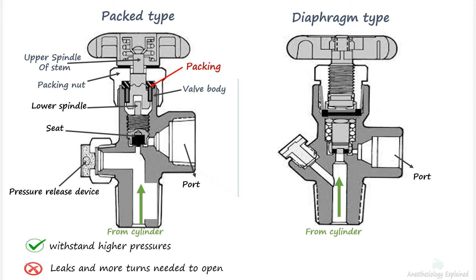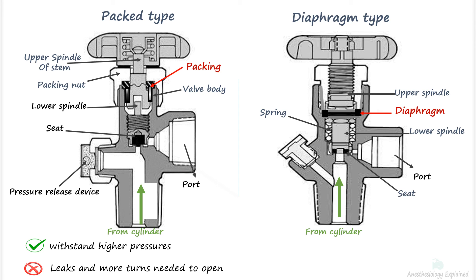Conversely, in a diaphragm valve, a diaphragm separates the upper and lower stems. The lower stem controls the gas flow by either shutting it off or allowing it to pass through the valve, and the lower spindle assembly is enclosed in a spring which pushes it away from the seat when the valve is opened. The upper spindle is threaded into the gland nut. The key advantage of a diaphragm valve is that it can be opened with just half or three-fourths of a turn, making it more convenient; however, these valves are less suitable for handling higher pressures.